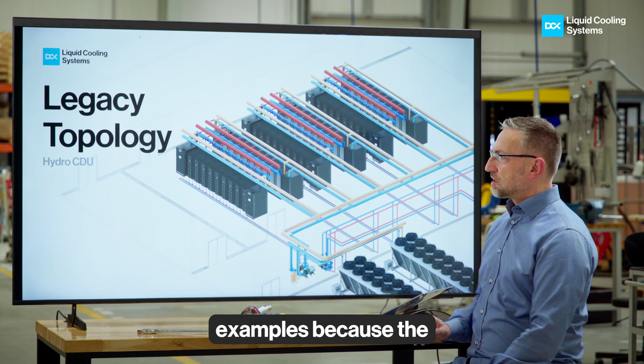It's all about the topology, honestly. I can give you a couple of examples, because the concerns or challenges regarding retrofitting come from the space inside of that data hall, inside of the white space. Imagine you have multiple rack groups, and you also have the containment, busways, bus bars, cable trays - and everything takes space, obviously. So you're trying to find the space, and the concern is related to the piping - how much piping I need, and where to put everything.